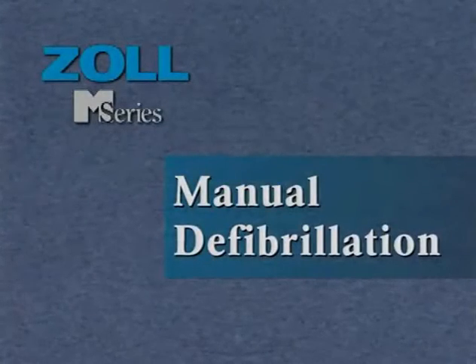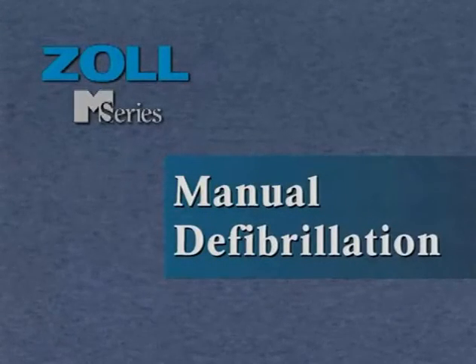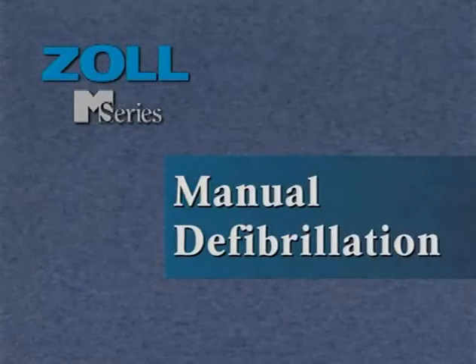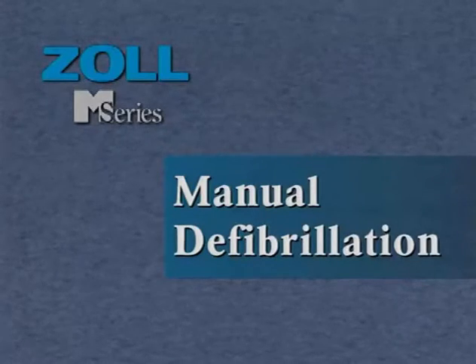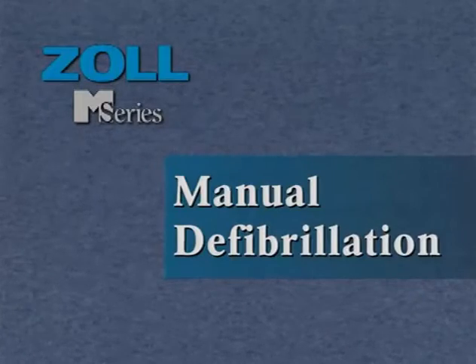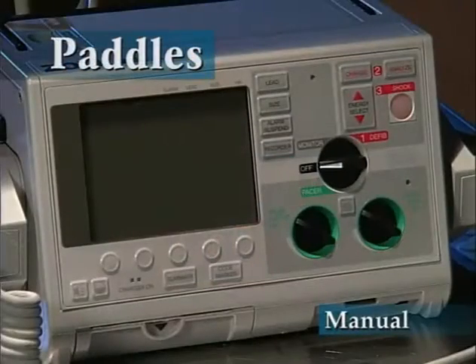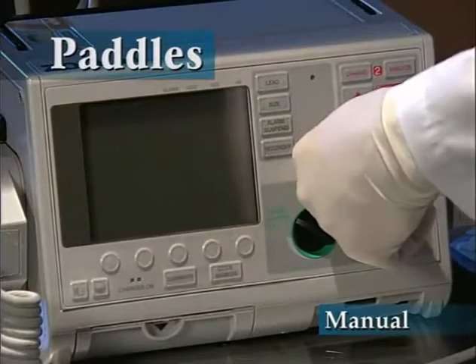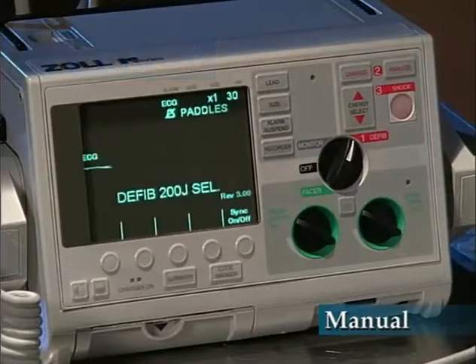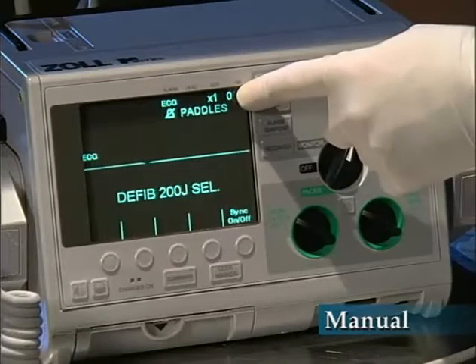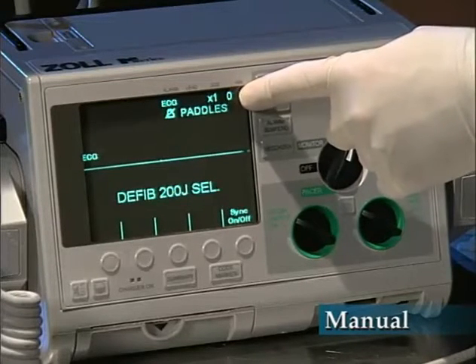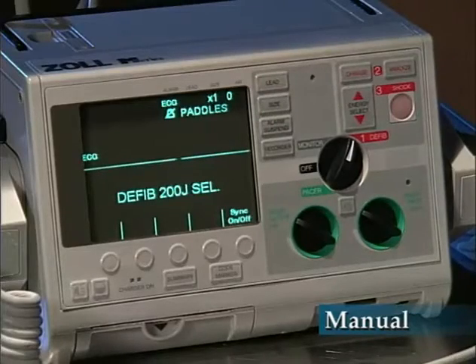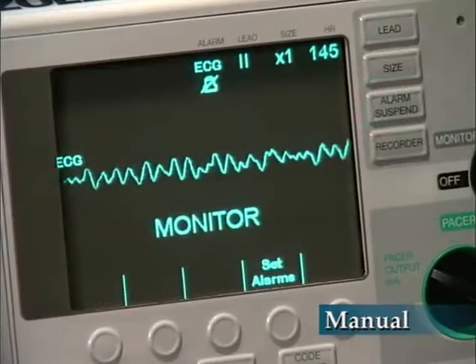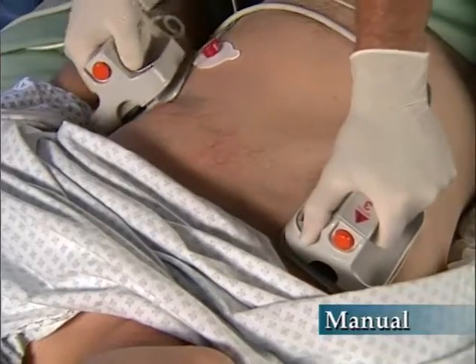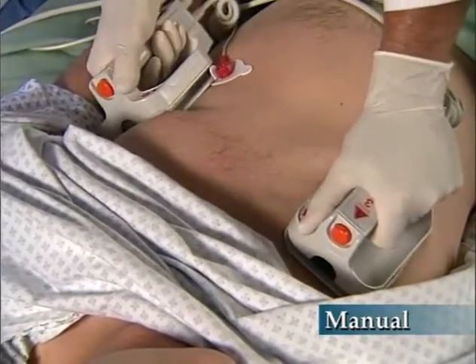This section is for personnel trained in manual defibrillation, advanced cardiac life support, or similar protocols. First, let's look at manual defibrillation with paddles. For emergency defibrillation with paddles, first turn the selector switch to defib. The unit defaults to paddles as the ECG source when it is turned to the defib setting, and paddles are connected to the universal cable. Observe the ECG by checking the monitor or use the paddles to quickly view the patient's rhythm.